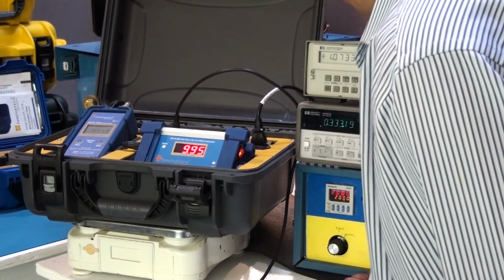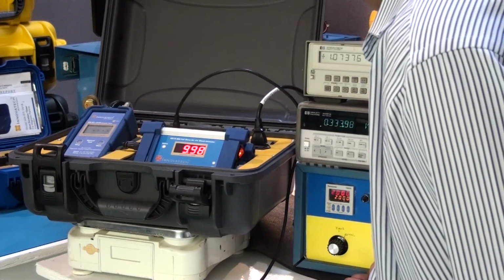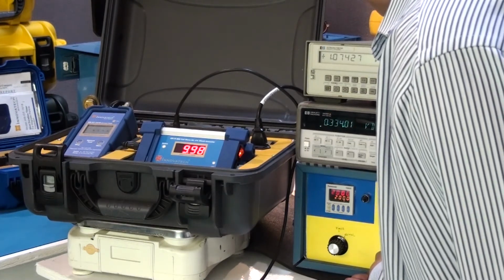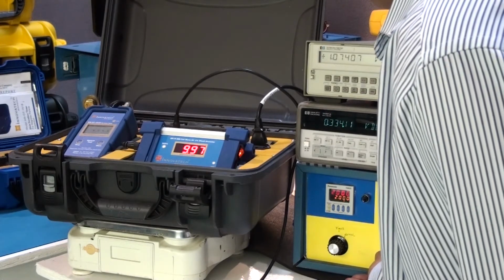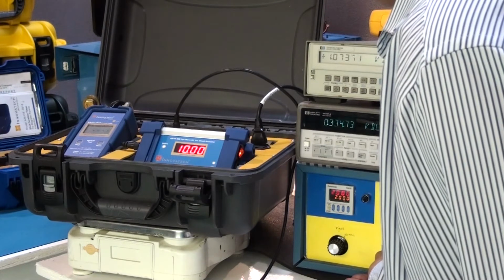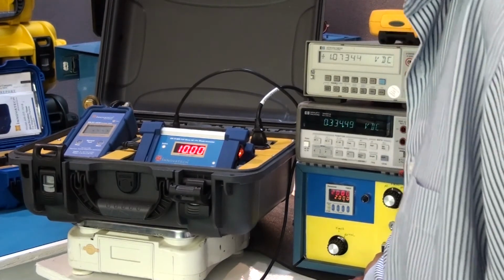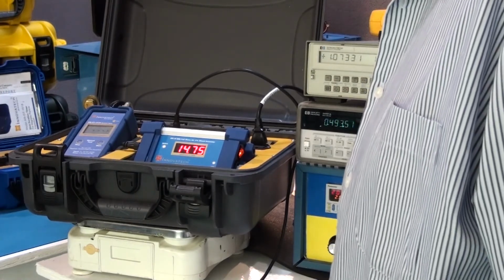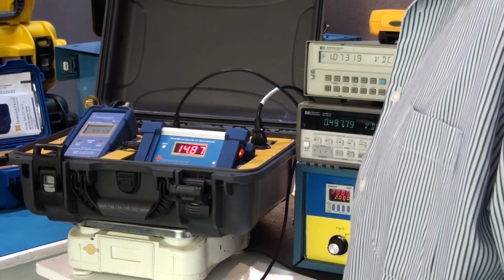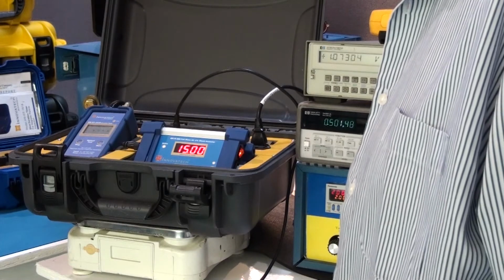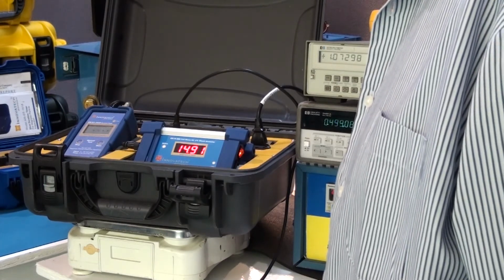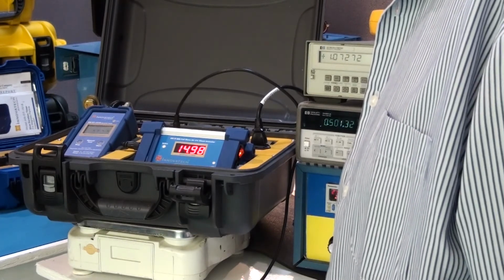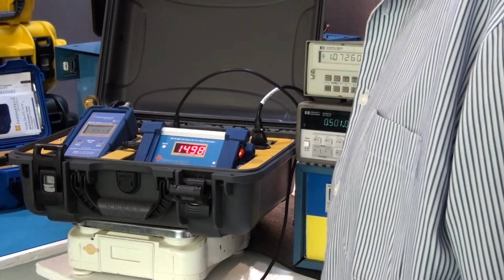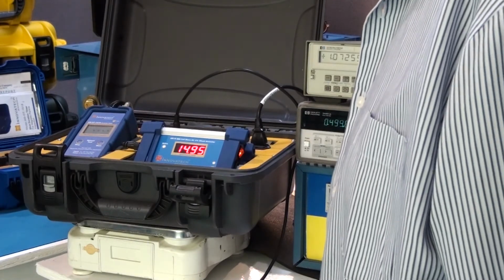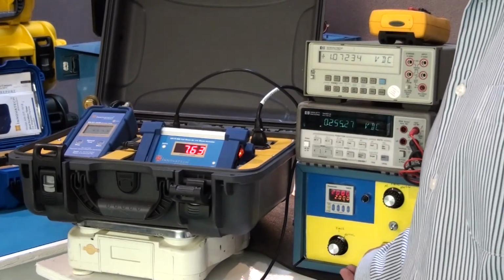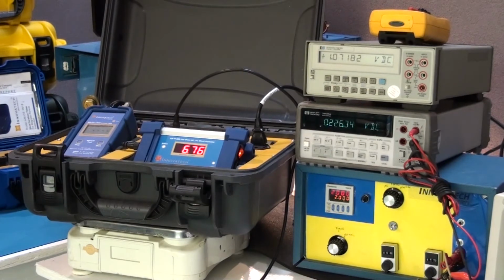So there we are, we're at about 3.3. And so we're at about 9.97. So that's well within spec. And let's run it up to 15K, which will be 0.500 on the voltmeter. So we can see we're about right there. 1495 to 1498, somewhere in that range. So that calibrates or verifies our calibration.